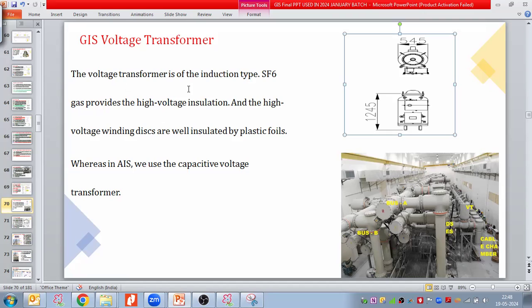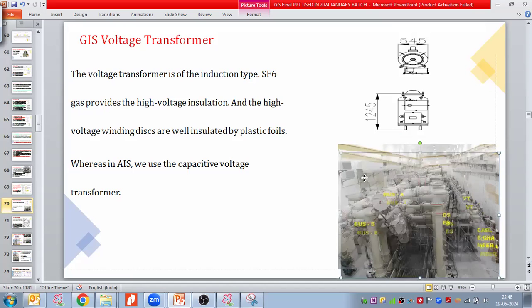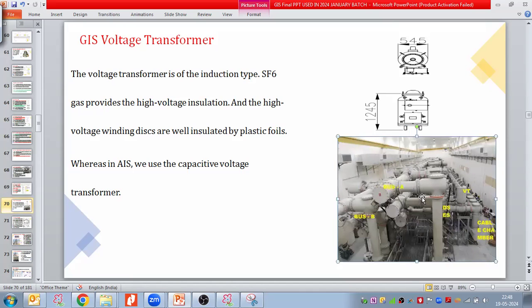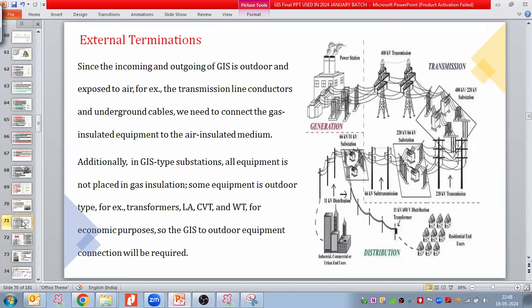So the VT is of the electromagnetic induction type. SF6 gas provides the high voltage insulation, and the high voltage winding discs are well insulated by plastic foils. For the AIS, we use the capacitor voltage transformer, right? The VT ratings and all these things will be as per the technical specifications.